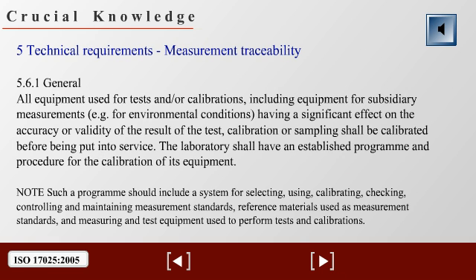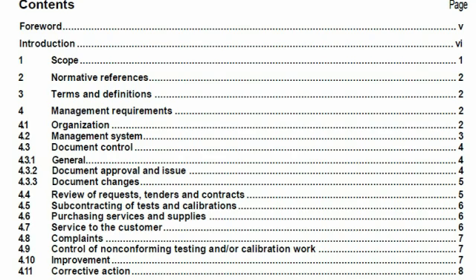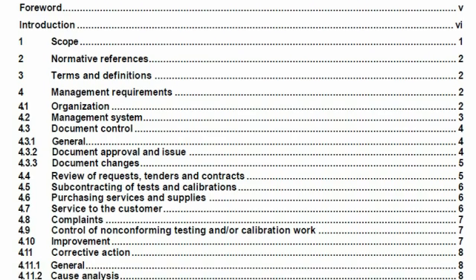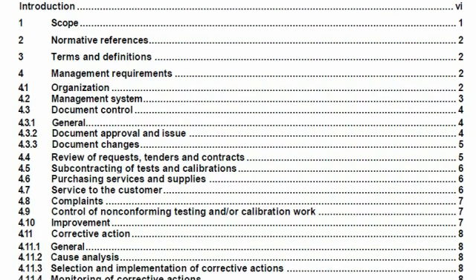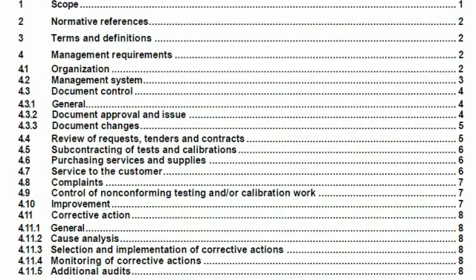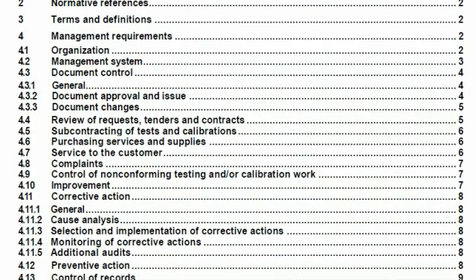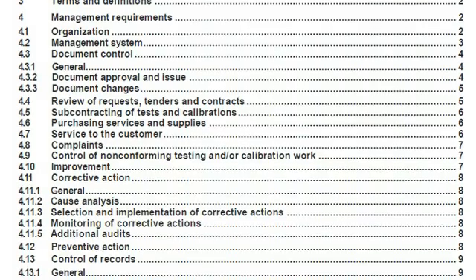The most common nonconformities found for Section 5.6 include using unapproved or non-accredited calibration providers and labs not calibrating equipment prior to putting it into service. Students go over the standard clause by clause and read and hear insightful comments, explanations, and applications relating to the real world of test and calibration labs.